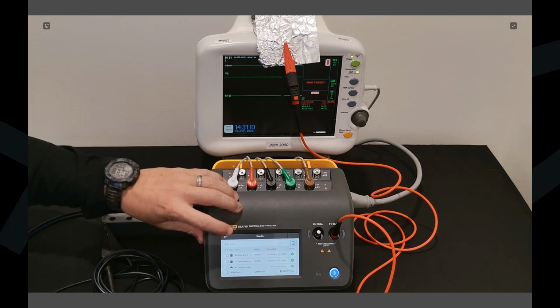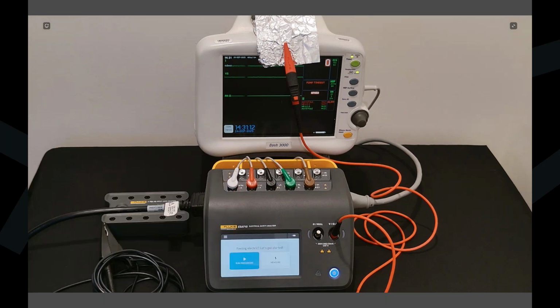So we've gone through an optimized procedure, but one of the things I want to show is you're not just limited to one procedure. Within OneQA Basic, you can have up to 5 procedures on the instrument, or with our OneQA Complete, you can have unlimited amount of procedures. So you can start building multiple procedures based on all the device types that you have. So if you just wanted to do a quick electrical safety procedure, if you were setting up where you're doing incoming inspection, right? You just did some devices came in, you shipped out to repair, you could just basically run a procedure, and set that up.